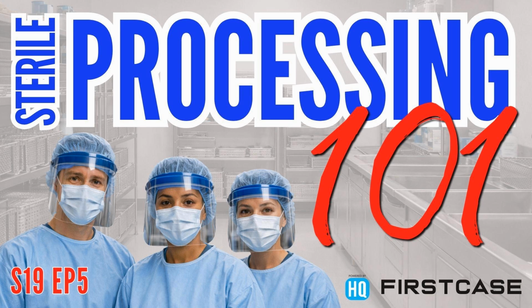So yeah, 4 minutes in the exposure phase of the cycle, but it takes a little bit of time to get up to that exposure phase. You've got about a half hour of drying and then up to a couple hours of cooling after the drying. So it takes a little while to get the instrument ready for use.